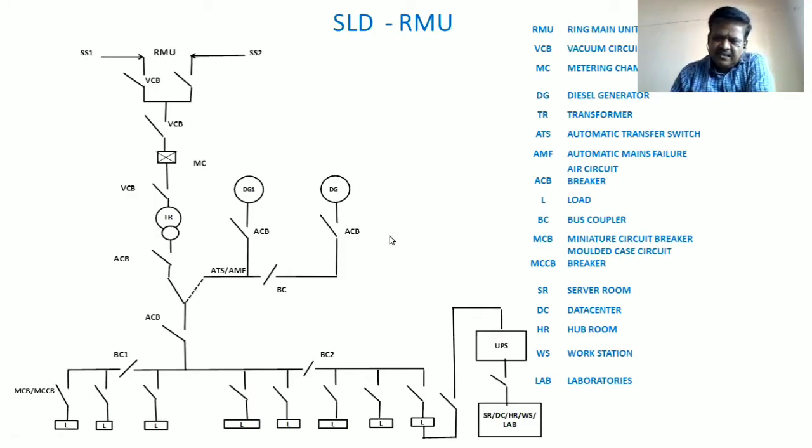Then after this process, the responsibility of the O&M, that is the operation and maintenance team, who is in charge of that shift, is to look after this, check these DGs and check different parameters, the diesel level and oil level and everything. And he has to take some readings also, and update the readings in the data center. After some time, after completing all these operations, he has to contact his EB persons and find out the reason for this power failure.